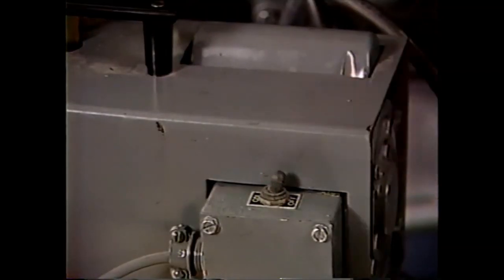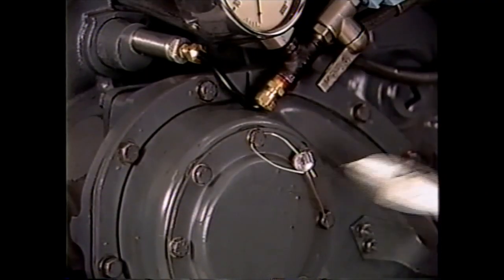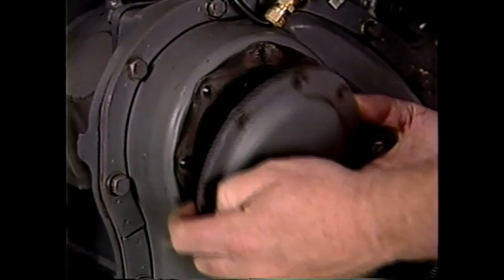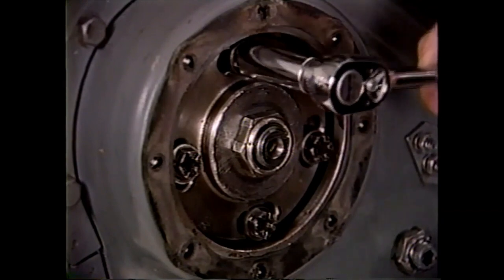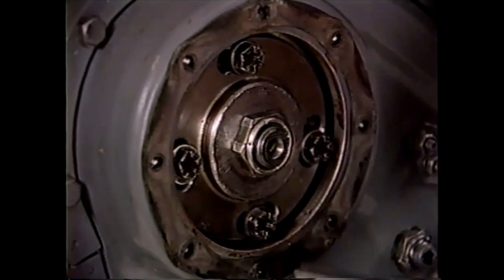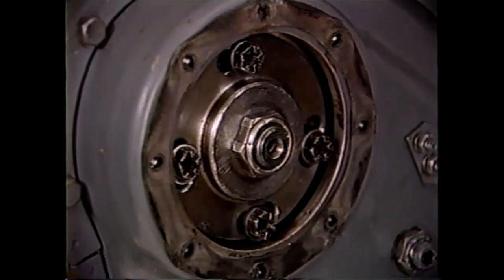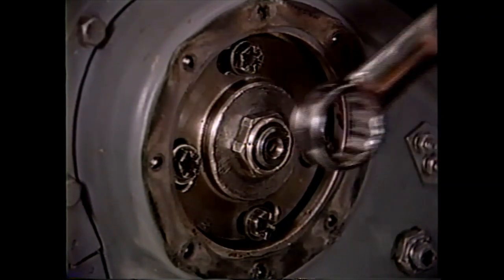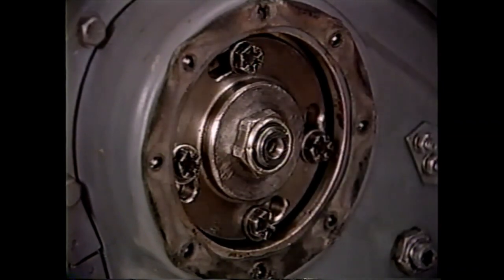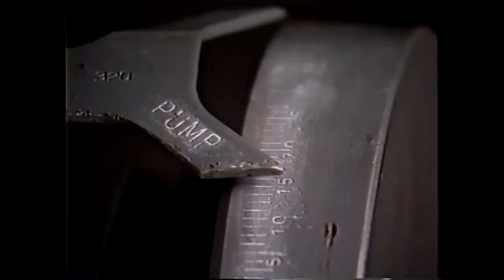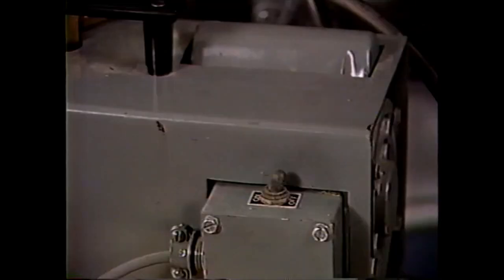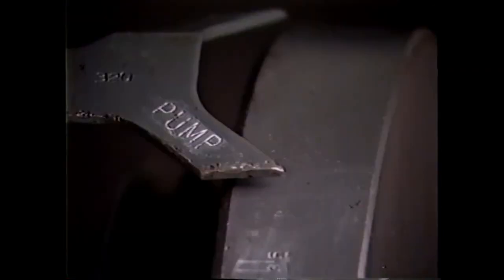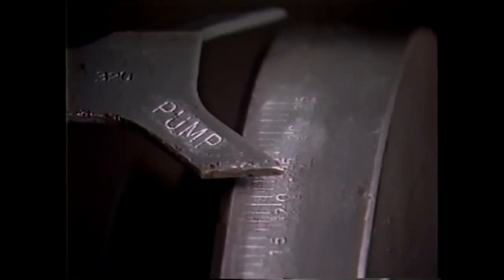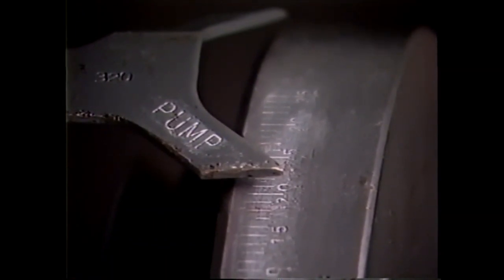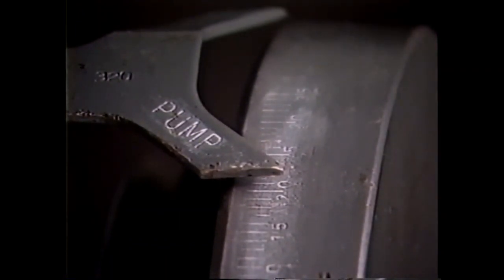Shut off the high pressure timer. Remove the seal on the pump gear cover and remove the cover. Loosen the pump gear bolt slightly to allow the gear to move on the drive hub. Turn the pump cam counterclockwise until the gear bolts are at the ends of the adjusting slots. Then turn the crankshaft counterclockwise at least 45 degrees. Turn on the high pressure timer and rotate the crank clockwise until the pump pointer is aligned with the proper timing specification on the damper.